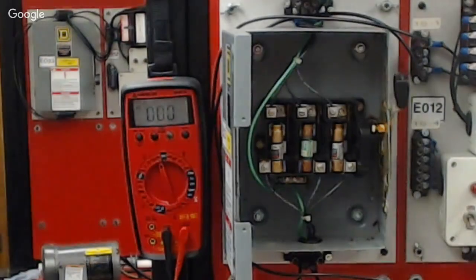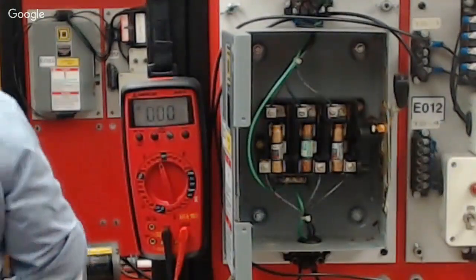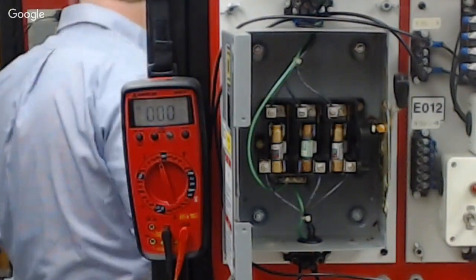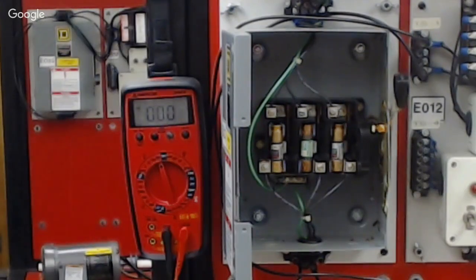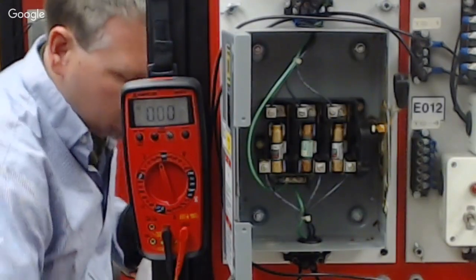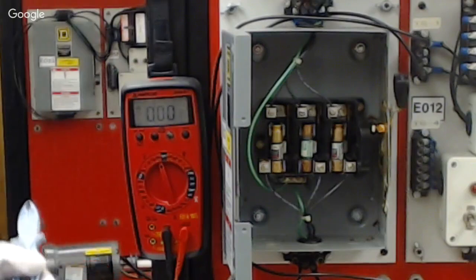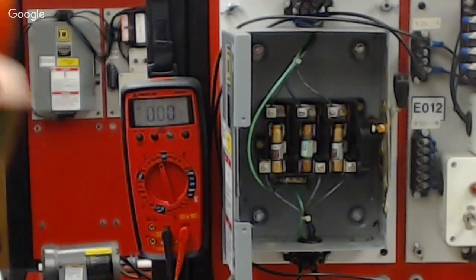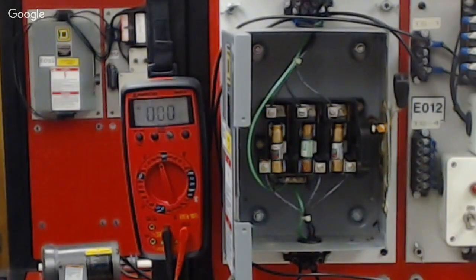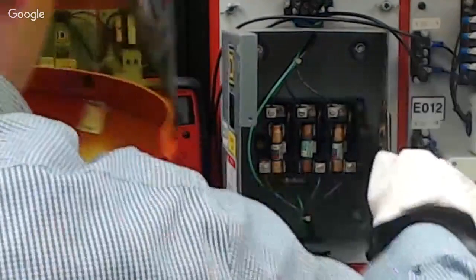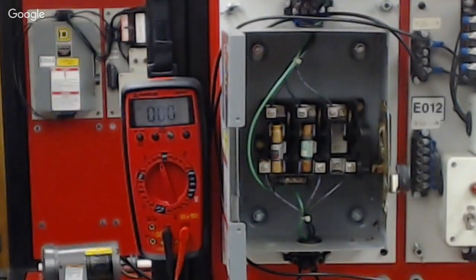We have a three-phase system here. So if there was an issue, we would be reading 120 volts on this system. Let's look at it when I insert a bad fuse into this system. We're going to pull this off. We're going to remove this, and I'm going to insert a bad fuse.